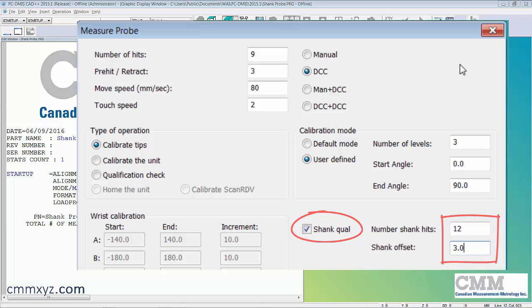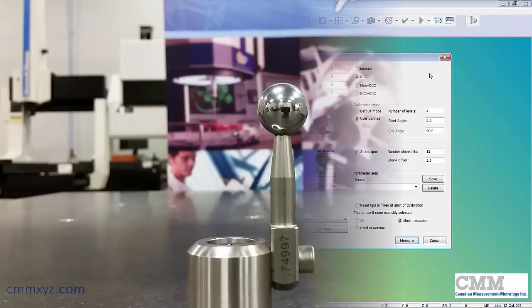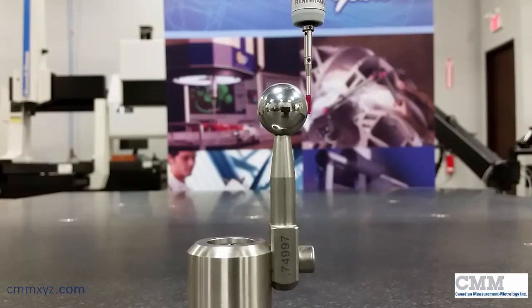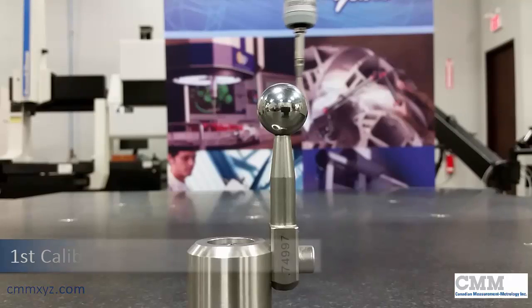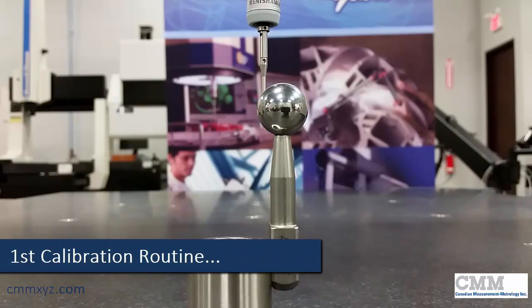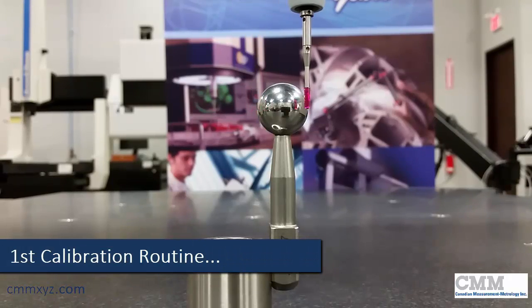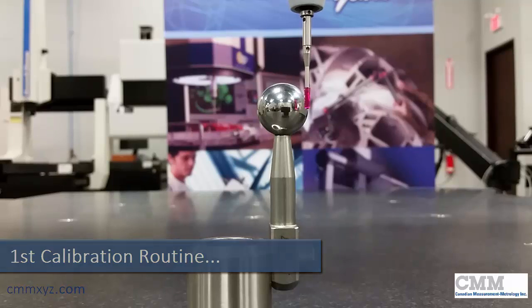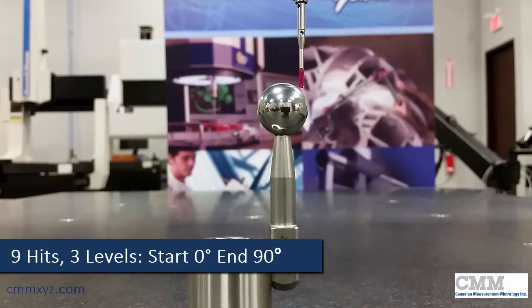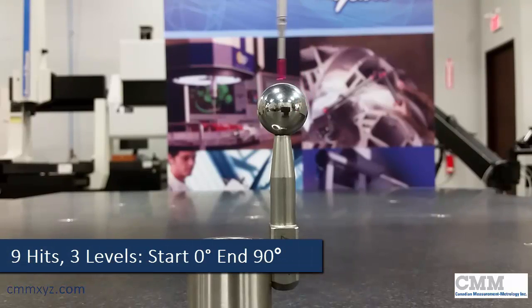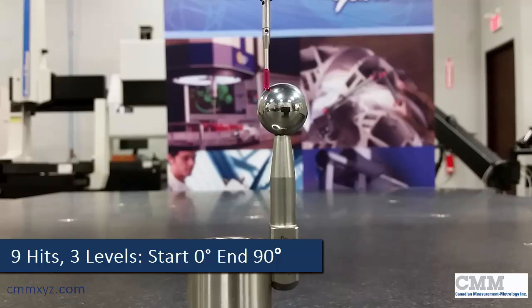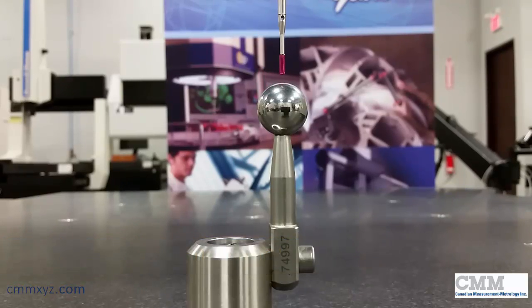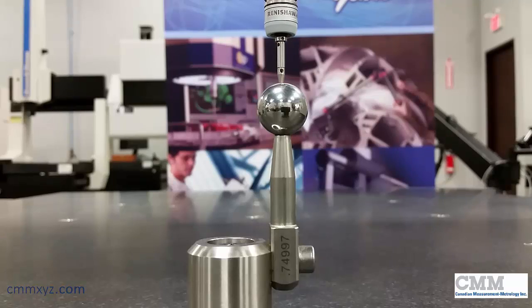Let's run the calibration and I'll talk you through it. We're all set up to calibrate here. Here's our regular calibration routine. These are the nine hits, start angle zero. There's the second level of our three levels, and it will finish on the top at the north pole. That's done.